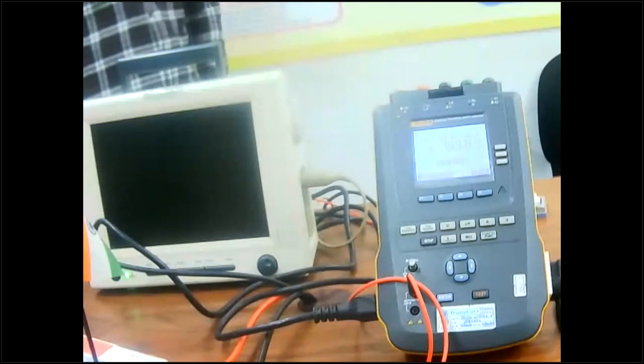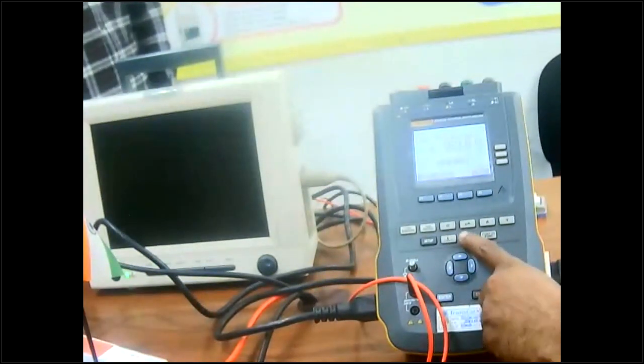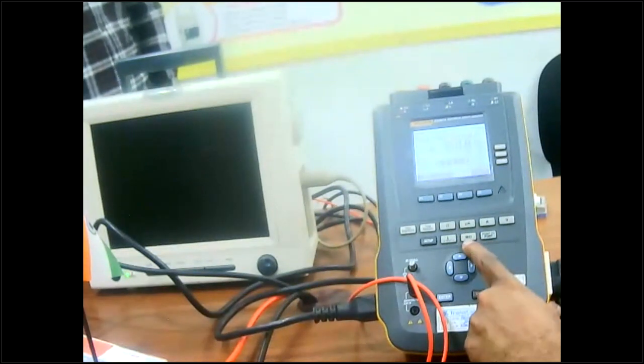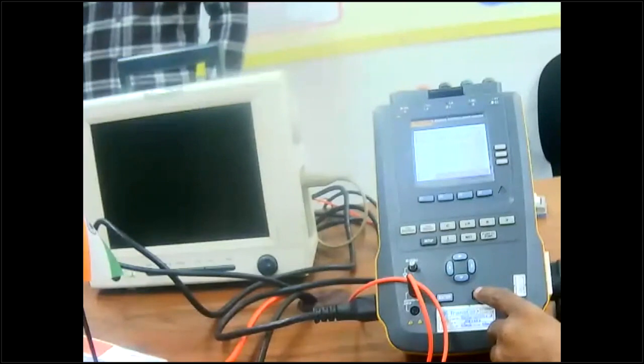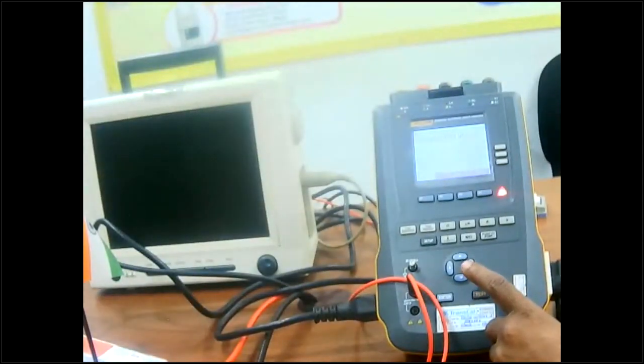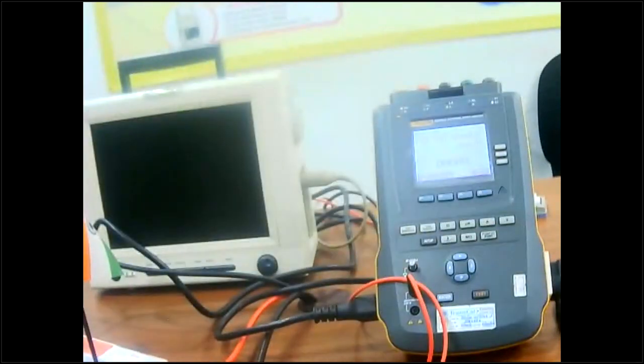Now I am doing mains on applied parts. To do that, just press the megaohm button. You are able to see this. You can press it and then do the testing. Please be aware whenever you are going to do the testing. Sorry, Ravi, megohms is for the insulation test only, that is 500 DC or 250 DC. That is not the mains on applied part. Mains on applied part is done under the leakage current test, under microamperes, and there should be a mains on applied part test under that setting, probably through the more button to get to it.